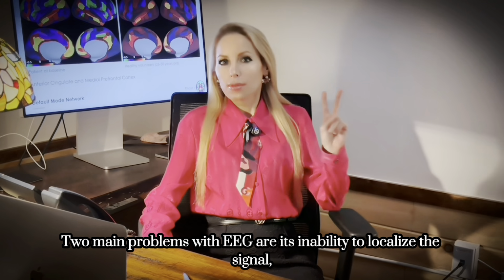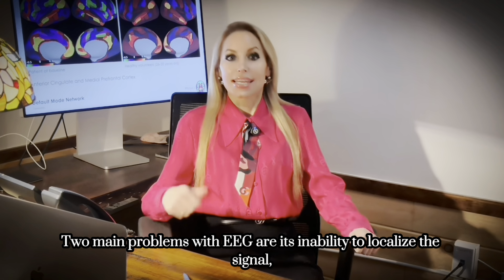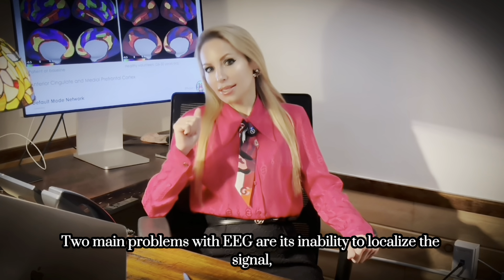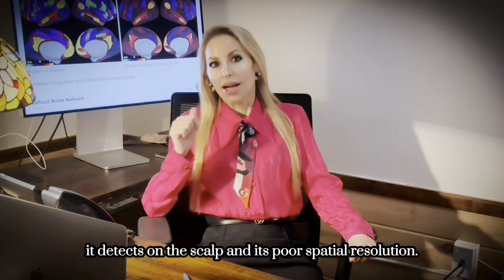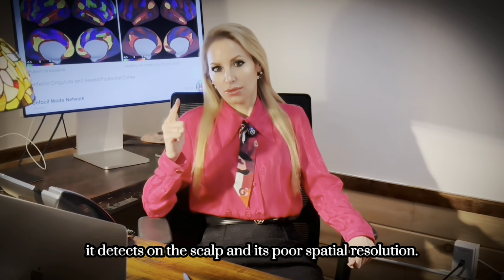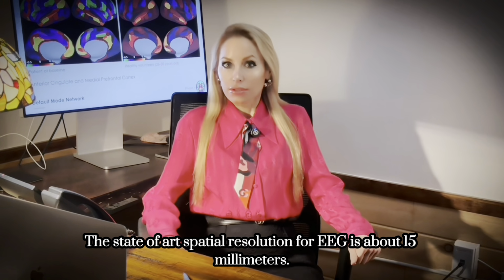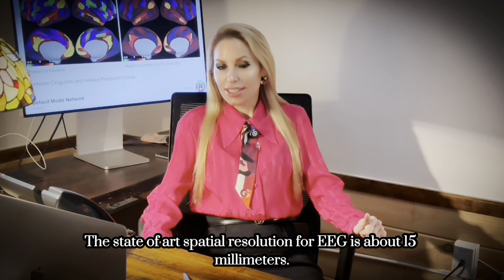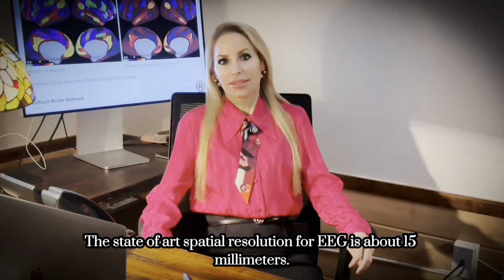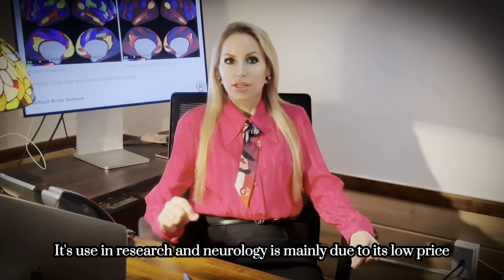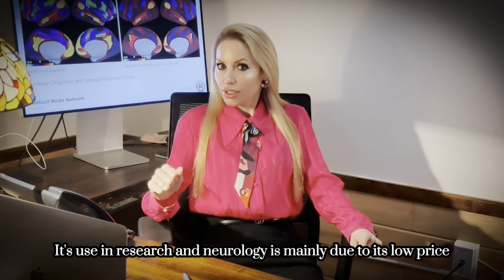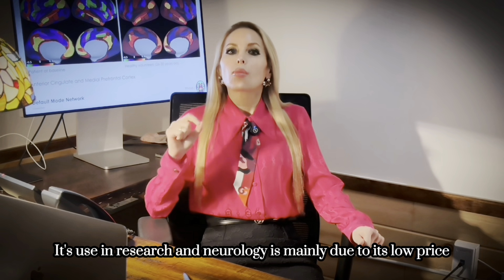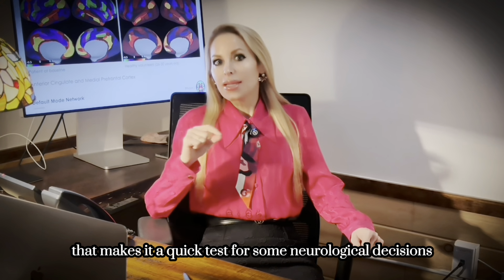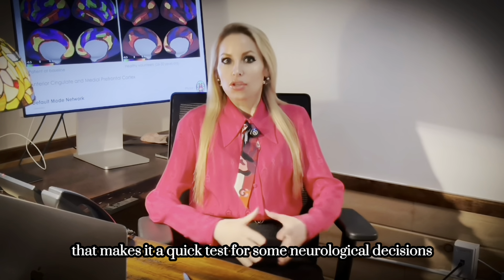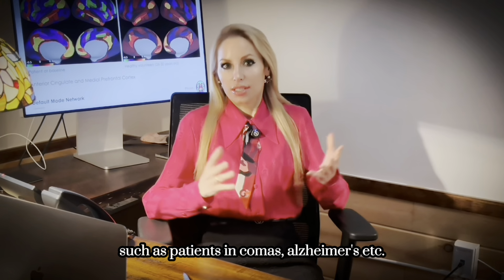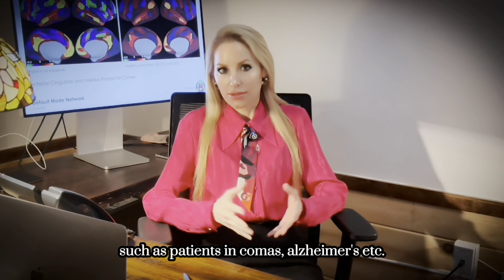Two main problems with EEG are its inability to localize the signal it detects on the scalp and its poor spatial resolution. The state-of-the-art spatial resolution for EEG is about 15 millimeters. Its use in research and neurology is mainly due to its low price and ease of use that makes it a quick test for some neurological conditions such as patients in coma, Alzheimer's, etc.